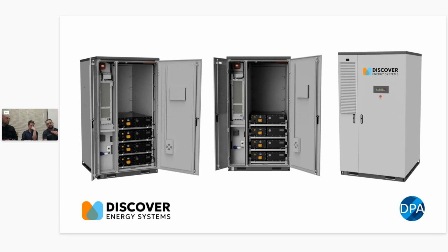So the unit of scale with a 210 is 200 kilowatt hours, 4 packs, each of those packs is 53 kilowatt hours. Up in the top left-hand corner you can see the thermal management system, which circulates the glycol around the cabinet. In the bottom left-hand corner is where all the DC distribution comes in, and the AC connection powers the thermal management system and the UPS system. At the top you'll see a bunch of fire detection stuff.